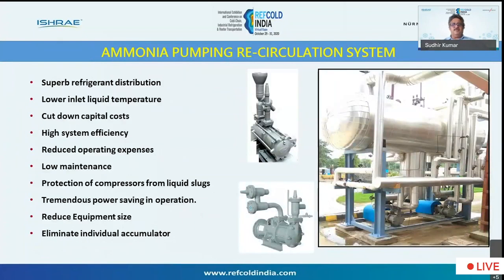And after finishing with evaporative condensers, the next important aspect is the ammonia pumping recirculation system. This recirculation system has been used in dairy plants for more than 10-15 years, and they have found a lot of advantages in the system. The first and foremost advantage is superb refrigerant distribution. In olden days, you were expected to throttle the valve and expect to flood the coils. Whereas in this, it is all done automatically and it is pumped through.